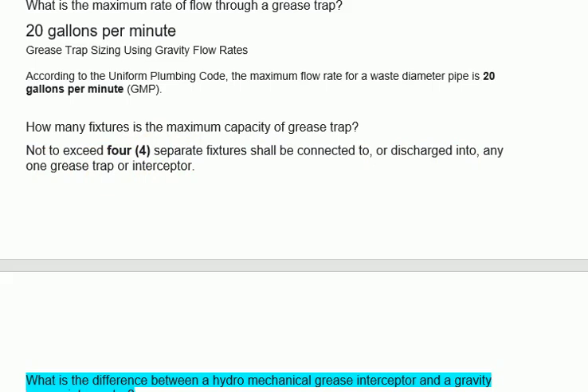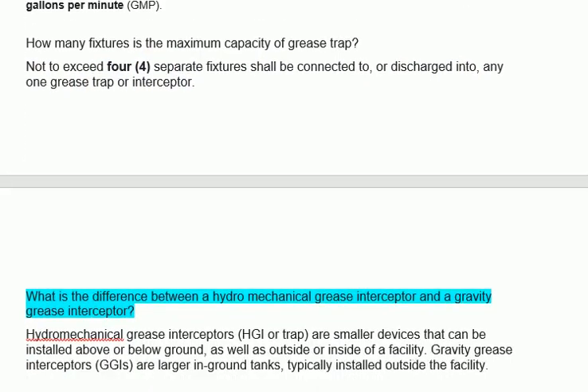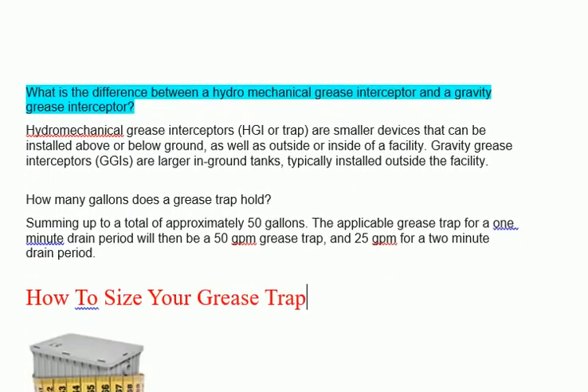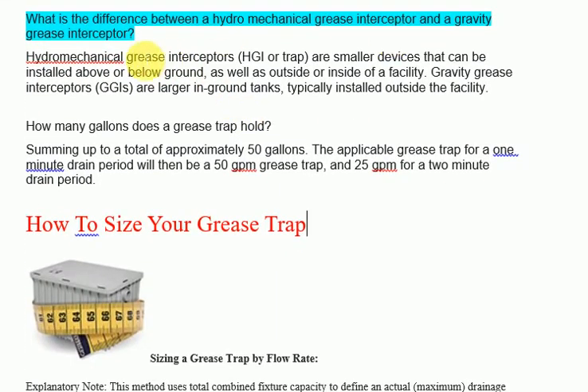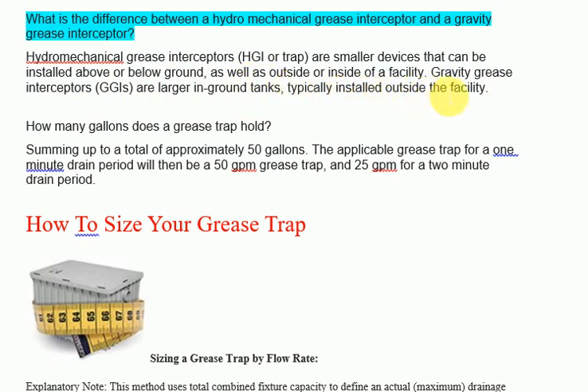What is the difference between a hydromechanical grease interceptor and a gravity grease interceptor? Hydromechanical grease interceptors (HGI) are smaller devices that can be installed above or below ground, as well as outside or inside a facility. Gravity grease interceptors (GGIs) are larger in-ground tanks typically installed outside the facility.